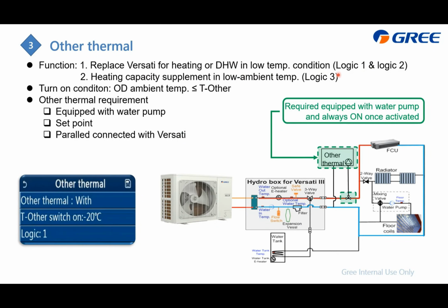As for the logic 3, it can work together with the VERSATI, which is a supplement. And what you can set is this one, this outdoor ambient temperature. If it is lower than, for this case, lower than -20, then we will activate this other thermal. And also this one, you need to tell the system whether you have this one or not. And here is select to follow which logic.